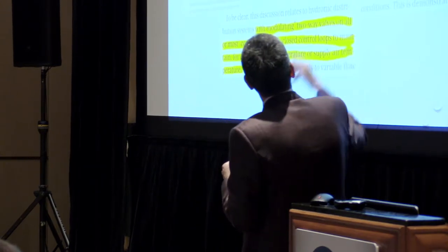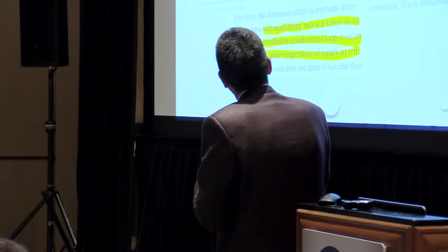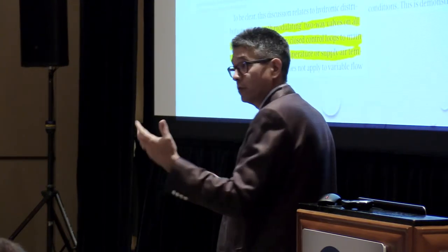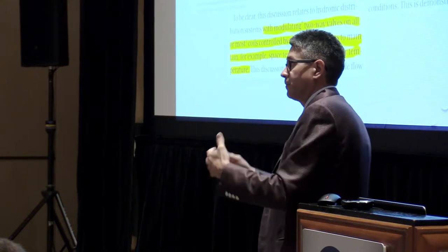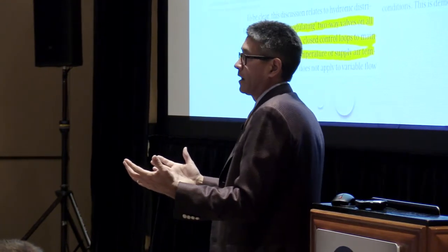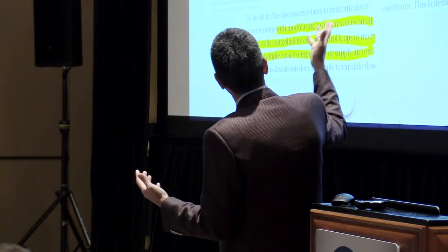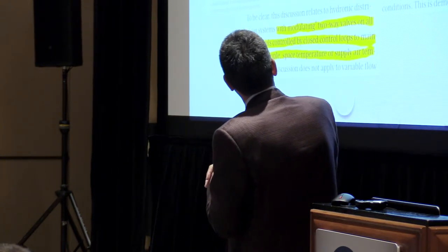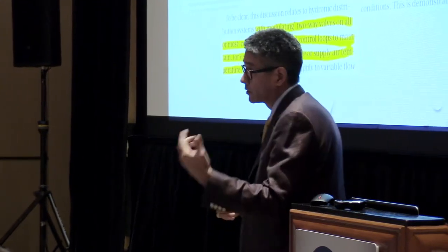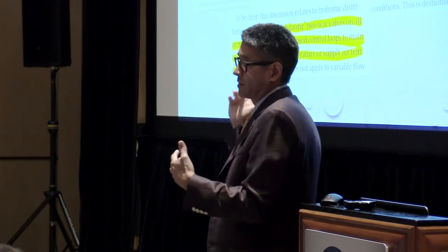Understanding those caveats, he goes back in further and says the key thing: the system can only be manually balanced for one flow condition, and that's what we were just saying. If you set it up and open the whole thing up and it has diversity, what condition are you going to balance it in? That's where he says it's not even clear how to balance a system with diversity. How are you going to do it? So, a lot of good takeaways from that article.